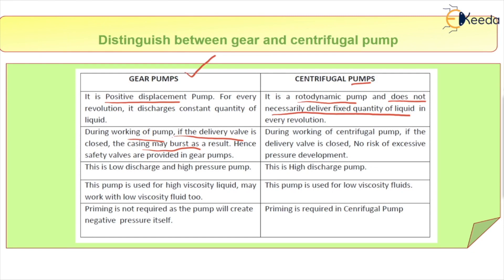In the case of a centrifugal pump, it is not necessary to worry if the delivery valve is closed, because there is no risk of excessive pressure development — the liquid simply recirculates inside. Also, the gear pump is a low discharge, high pressure pump, whereas the centrifugal pump is a high discharge pump. Comparatively, the centrifugal pump gives higher discharge.